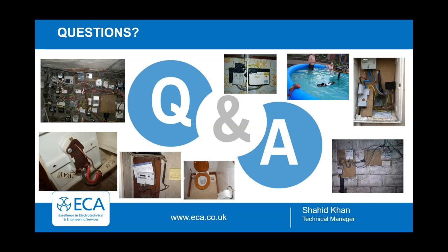Okay, thanks. Oh, we've got a good one here from Gary about main bonding cable size can be an issue. Again, going back to the ESF best practice guide for your bonding, if there's nothing whatsoever, none being put in, and it's needed, that's a C2. If there's something in and it's adequate, showing no signs of stress, damage, thermal damage, etc., that's usually a C3. I'm guessing Gary at 11:42 AM was talking about PME installs with a 6mm bond. Quite often that's a C3, unless you can see any signs of harm.